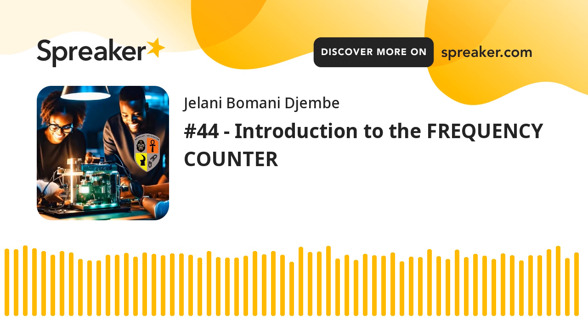Next, technicians should use a known reference signal to verify the accuracy of the frequency counter. This can be done by connecting a signal generator or any other known frequency source to the frequency counter and comparing the reading with the expected frequency.